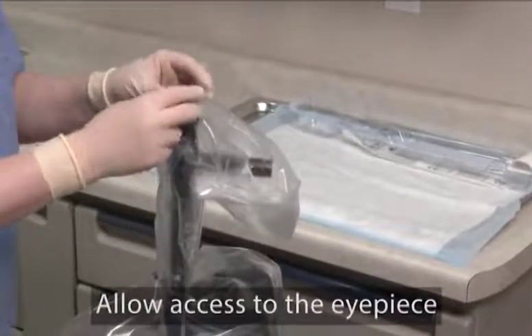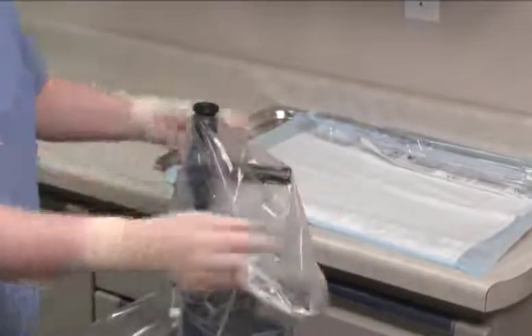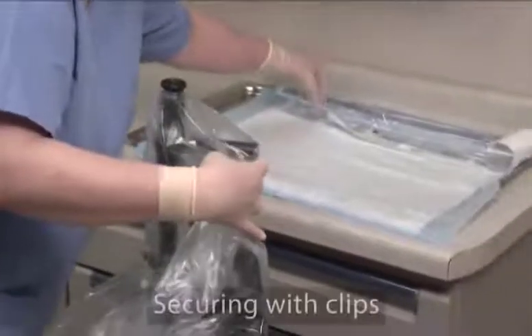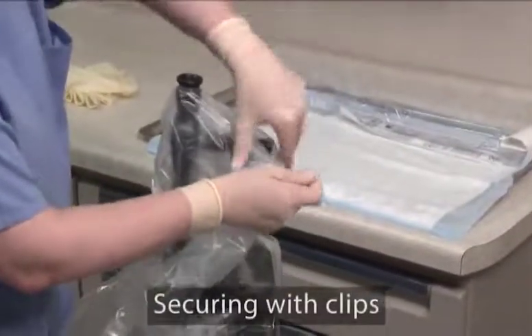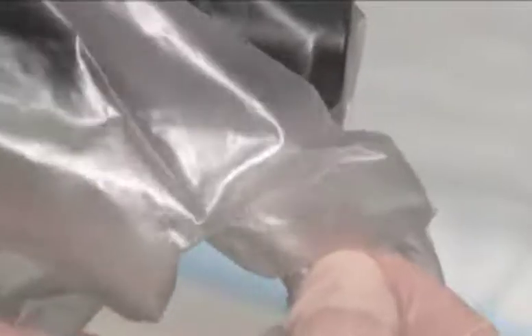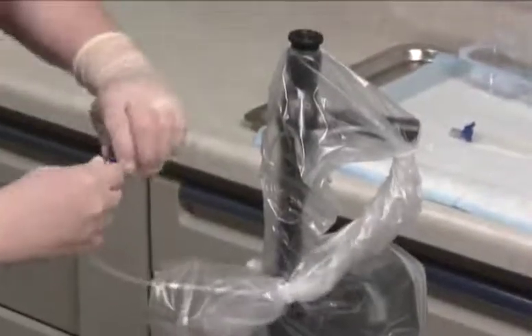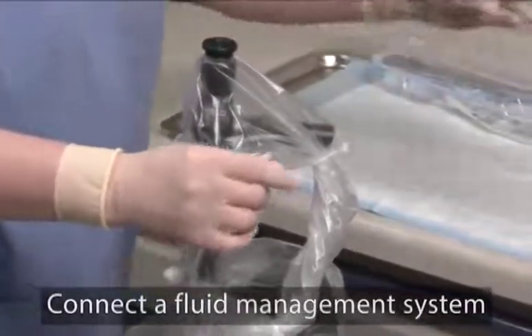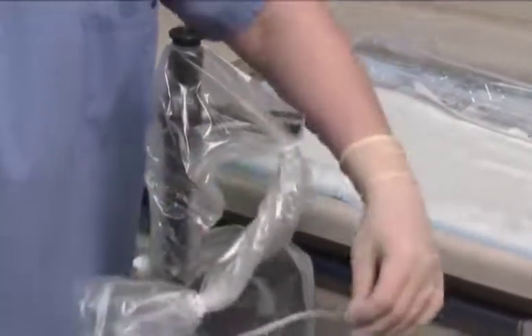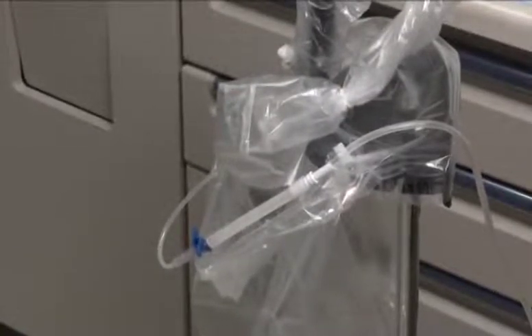Align the eyepiece opening of the control body cover with the cystoscope eyepiece and pull down on the cover to allow the eyepiece to protrude through the opening. Secure the control body cover and irrigation tubing to the light guide cable by wrapping or twisting the cover around the cable and securing with the clips. Next, remove the cap from the irrigation tubing luer lock and connect a fluid management accessory. Note that fluid withdrawal and irrigation may also be accomplished by connecting to a standard luer lock fitting on the accessory port. The cystoscope is now ready for use.